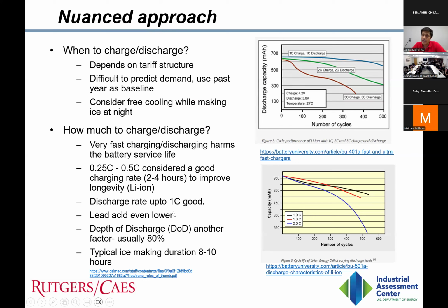Discharge rate up to 1 C is good — it can be an hour, but in most software, which I'll go to next, we have time. So in most software you'll see a default value of 0.5 C. Lead acid batteries are even lower — this 0.25 to 0.5 C is mainly for lithium ion batteries. Lead acid batteries are really low, like 0.2 or something. And the depth of discharge is usually 80%, so we oversize — we cannot completely drain the battery. We usually size the battery so that 80% is useful energy, and the 20% is still left.